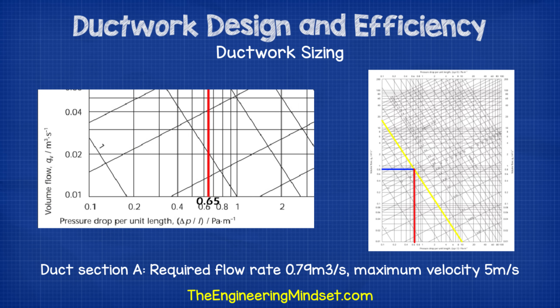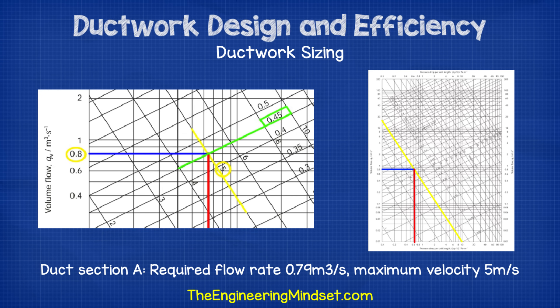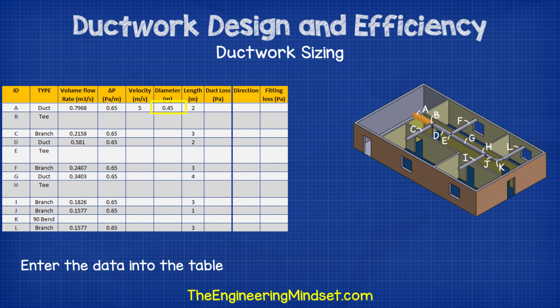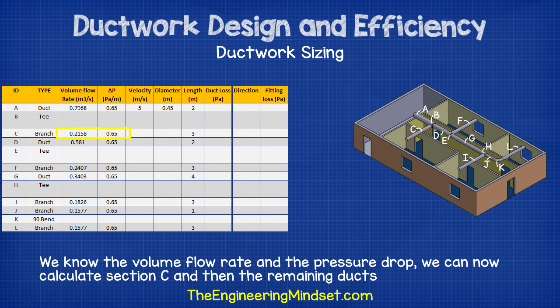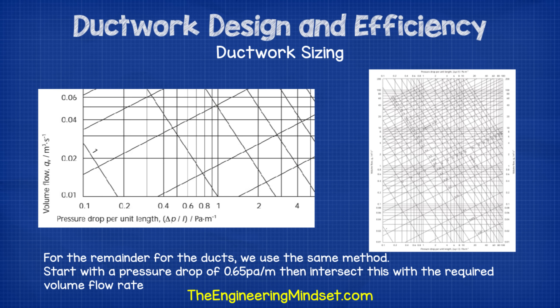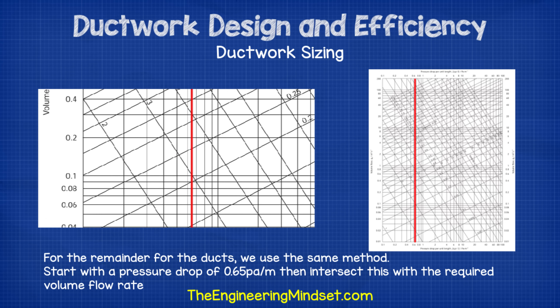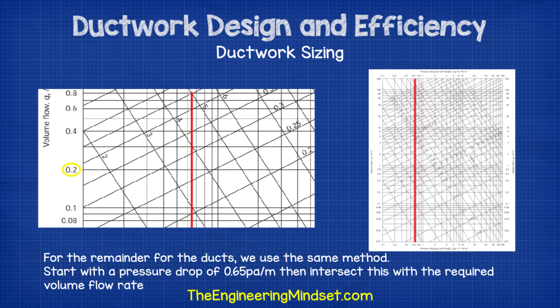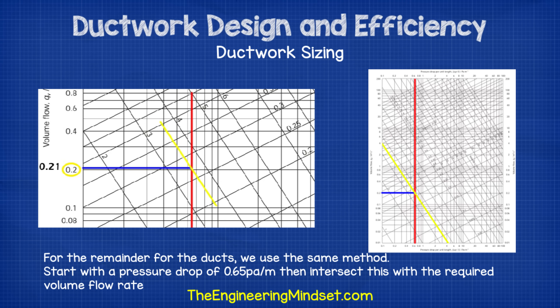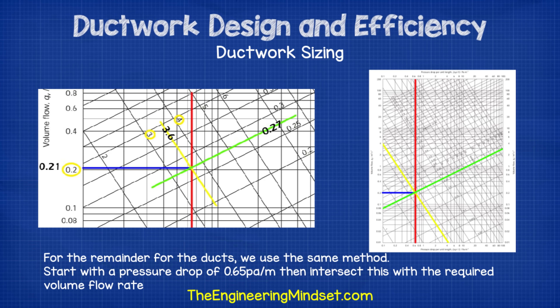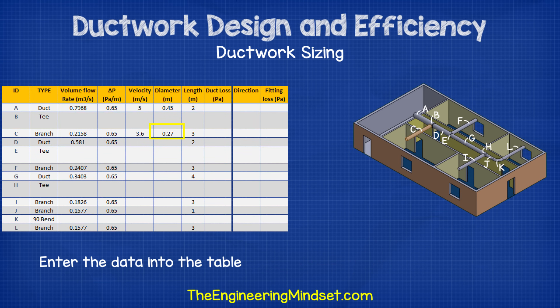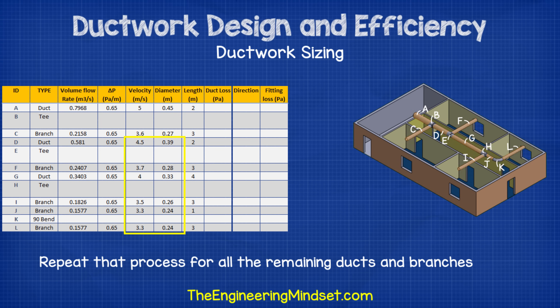We know the volume flow rates and the pressure drop, so we can now calculate the values for section C and then also the remaining ducts. On the chart, we start by drawing a line from 0.65 pascals per meter all the way up, then draw another line across from where our required volume flow rate is. For section C, we require 0.21 cubic meters per second. At this intersection, we draw a line to find the velocity — it falls between 3 and 4 meters per second, so we estimate around 3.6 meters per second. Then we draw another line on the other diagonal grid to find our duct diameter, which in this case is around 0.27 meters. So just repeat that last process for all the remaining ducts and branches until the table is complete.